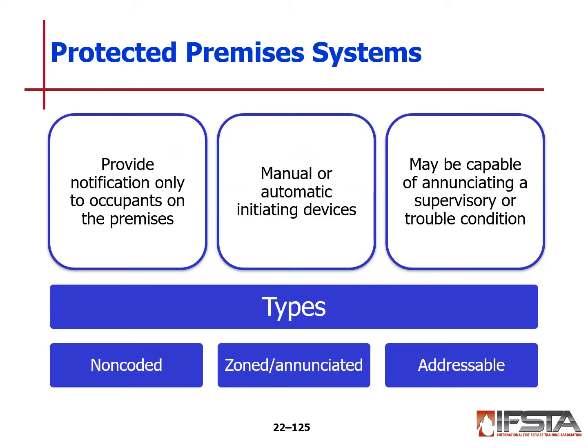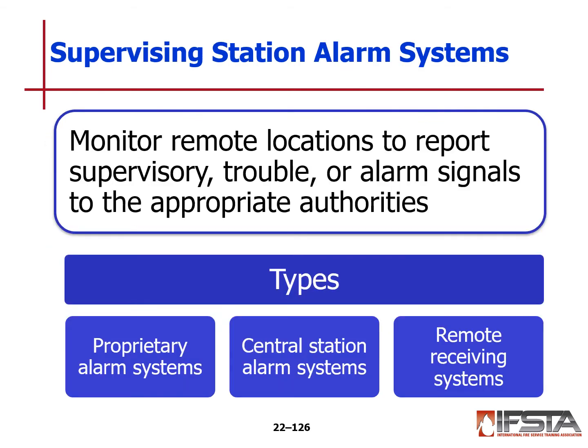Protected premises systems provide notification only to the occupants on the grounds, basically. These can be manual or automatic initiating devices and may be capable of annunciating a supervisory or trouble condition as well. There are non-coded, zoned, annunciated, and addressable types. Supervising station alarm systems monitor remote locations to report supervisory, trouble, or alarm signals to the appropriate authorities. These could be proprietary systems, central station alarm systems, and remote receiving systems.